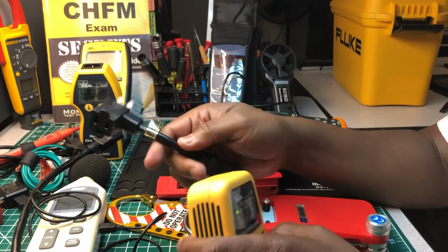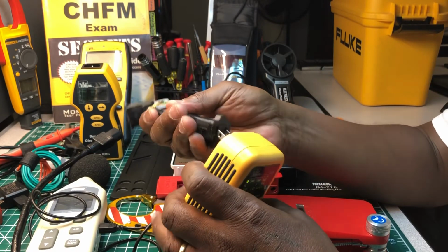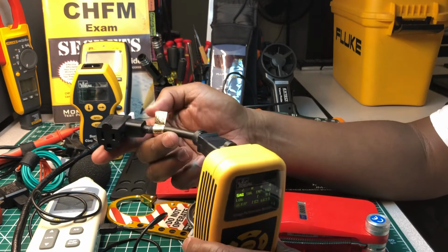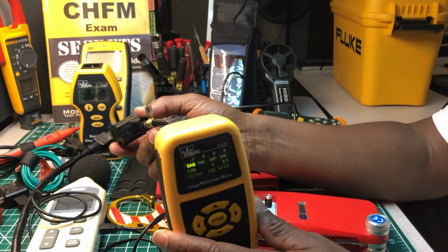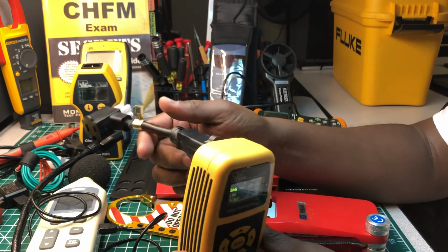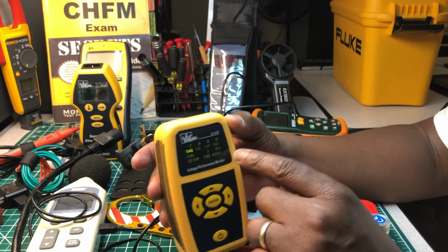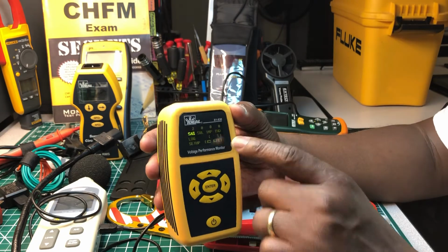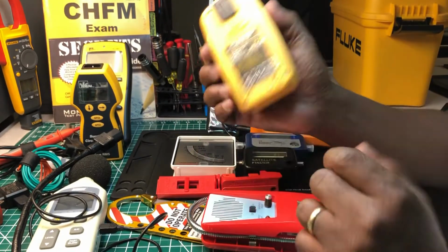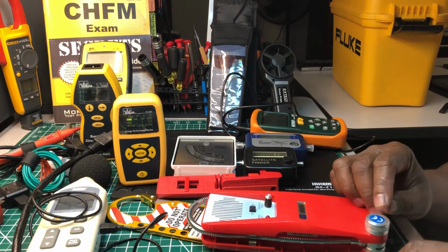So if I decide to, I can plug the machine inside of here, plug this inside of here, and then I could just analyze that outlet using this cord right here, and it'll tell me about the sags, the swells, the impulses, or the total harmonic distortion in that outlet, in that branch circuit, and you could just analyze that circuit, troubleshoot that circuit. So, this is a good instrument to have also. Very good instrument to have.